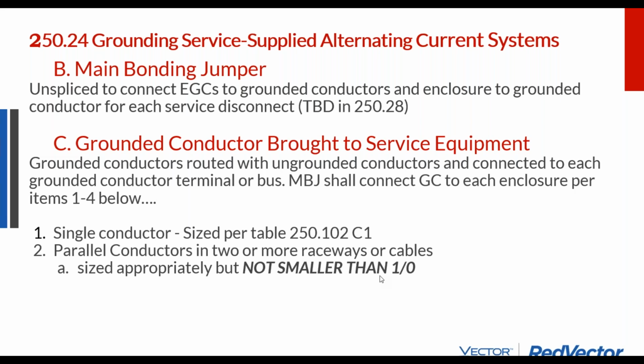When I open up electronics, I see parallel runs being made with wire that's less than 1/aught, but that's a listed UL assembled, manufactured assembled product that is using that parallel run behind the scenes. The difference is this is a parallel run that an installer is making out in the field as part of their kind of field designed and installed system. So parallel runs are only allowed for cables that are 1/aught or larger.